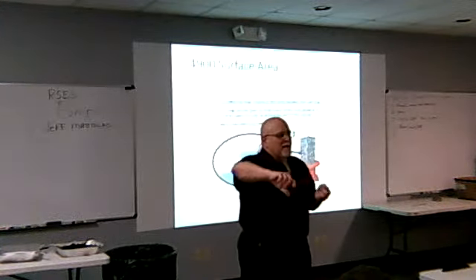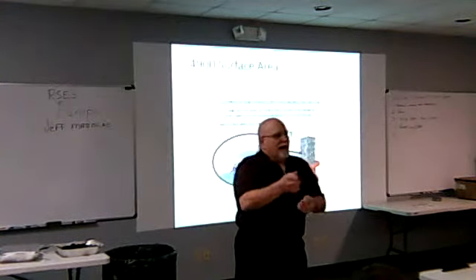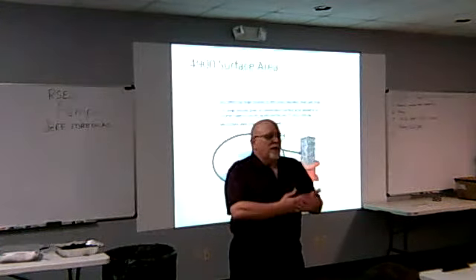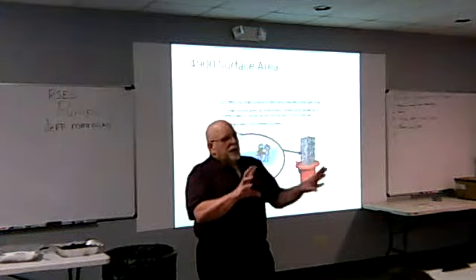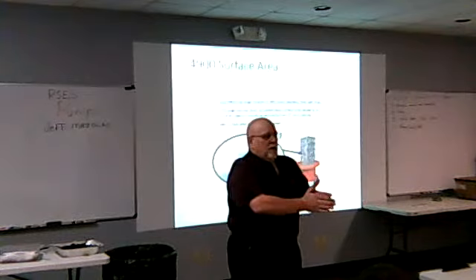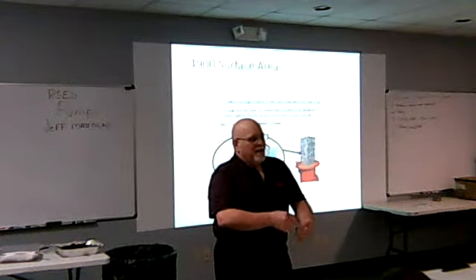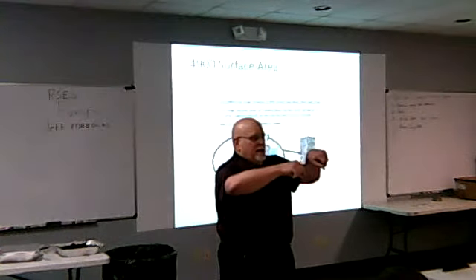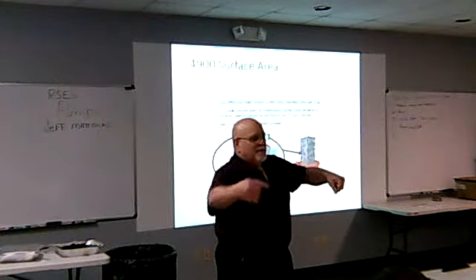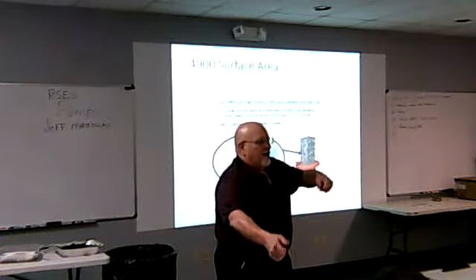The old Bell & Gossett was the old way because you had that little whiz wheel, because every time you turn that valve, you're changing the CV of the valve. I have to keep looking at my chart to get the CV. Bell & Gossett even went to the newer approach that Flow Design started. They have a venturi. This is Bernoulli's equation. If I'm at this point, I know I have this pressure at this flow. I choke it down, the velocity goes up, the pressure falls. So if I read that dimension, it's calibrated. I have a chart. If I get 2 inches here, I'm at 4 GPM. If I get 10 inches there, I'm at 15 GPM. I just throttle that ball valve to slow that velocity down to get that, and I'm done.